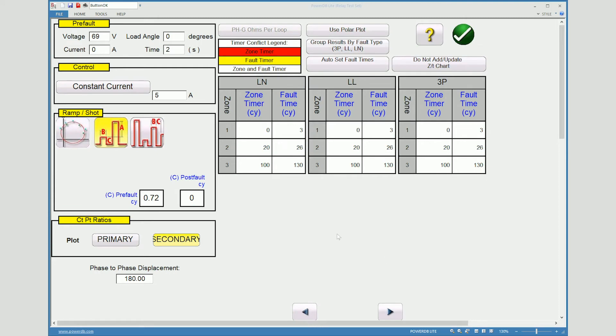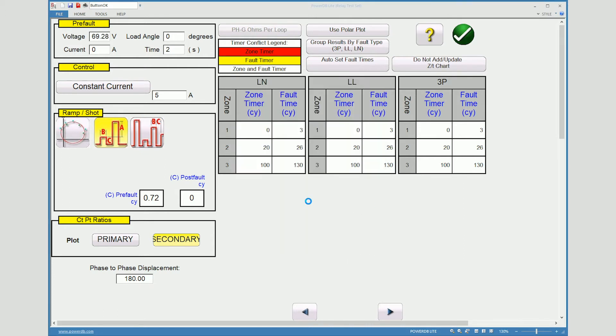This is going to allow us a few more pieces of information about how we want to proceed with this test. You have your pre fault values here. So our voltage will start out at 69 volts. You can define this wherever you would like. I usually try to keep it at the line to line of 120. So I've changed this pre fault voltage here. It will have no current and we'll also keep it on for two seconds before we'll actually initiate the fault on the test.